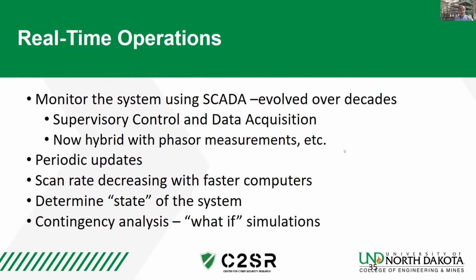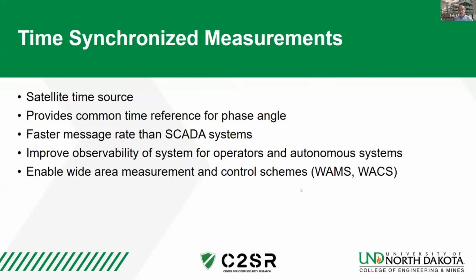These measurements are taken at high sampling rates and then communicated to the central control center with update rates of maybe seconds, though some measurements update faster. When these measurements arrive at the central control center, they're processed to determine the state of the system, and then a number of contingency analyses, or what-if scenarios, are performed.